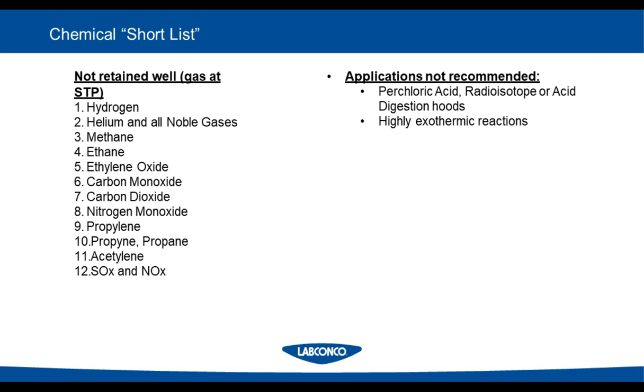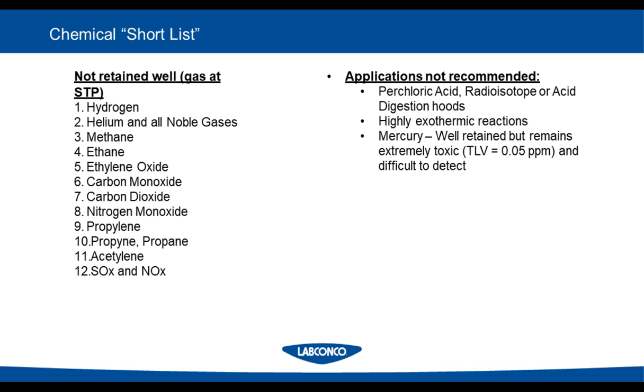That's not a problem. It's just that if it's a really exothermic type reaction, especially if it generates a lot of smoke, carbon filters do not capture smoke. The optional HEPA filters will capture most smoke particles. I think there would still be a slight smoke odor that would make it into the lab though. So these are, again, things to consider on the no-go list.